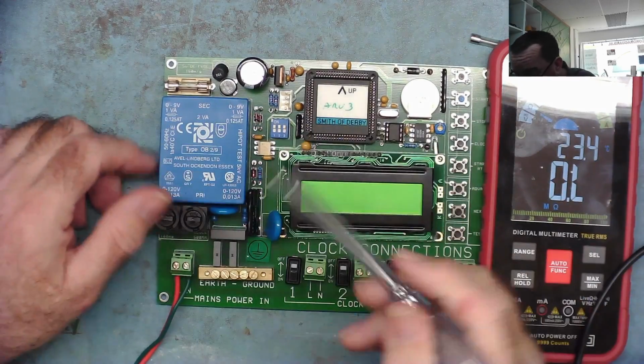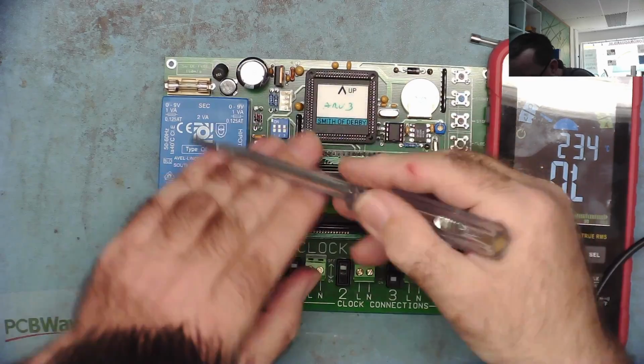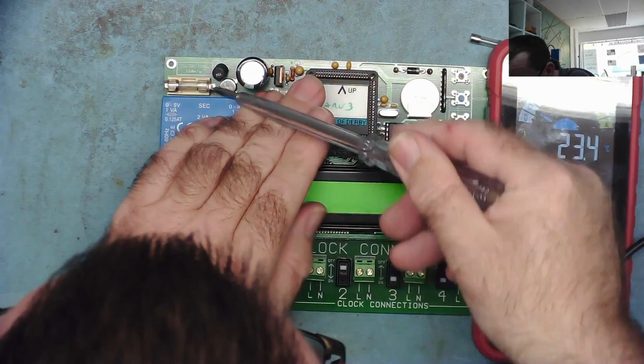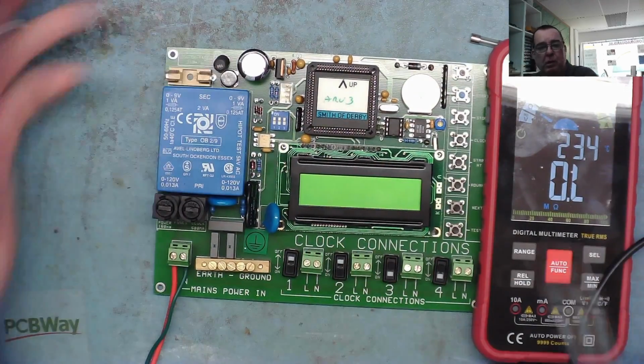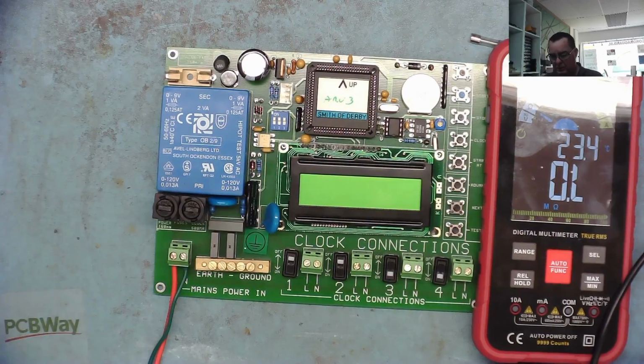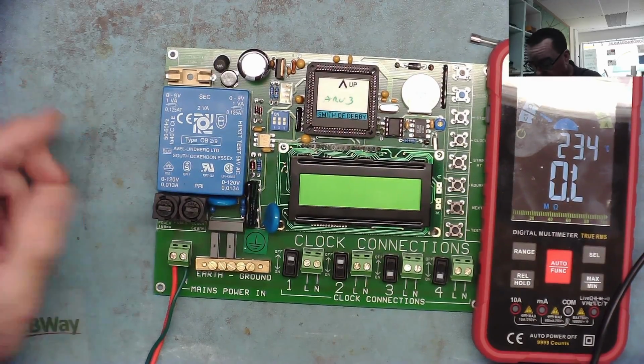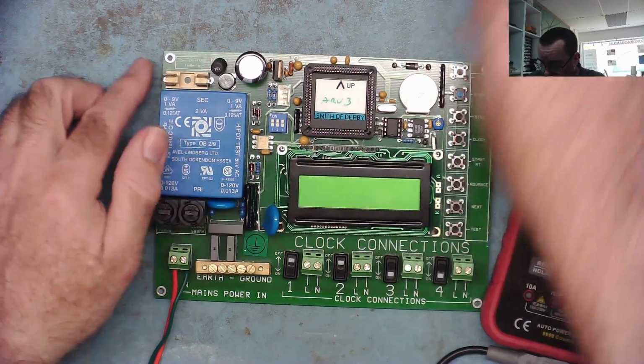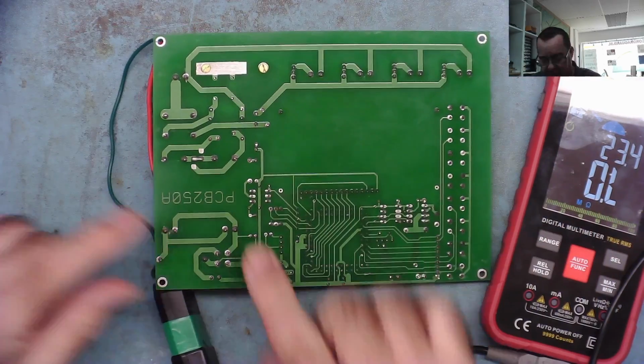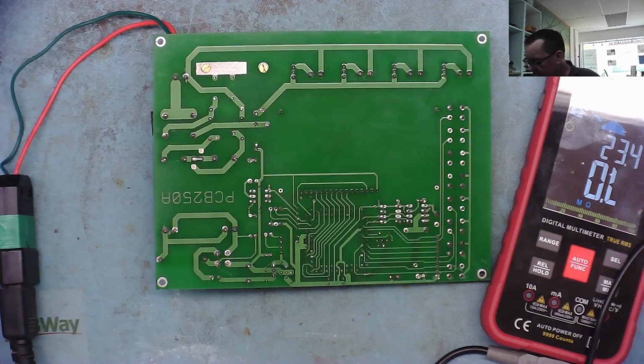Okay, let's remove this fuse. So now basically we have no load on the transformer, so the fuse shouldn't blow, and we should still be able to check if it's working by measuring directly across the secondary. So let's go with that.